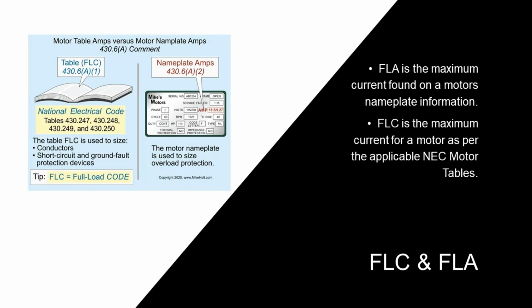All right, the only thing that we are going to size in motors with the nameplate is overloads. Conductor sizing is out of the code book. And I say overcurrent, I shouldn't have said that. I should say short circuit and ground fault protection is going to come out of the code book. Overcurrent is actually going to come out of the overloads. So I misspoke there. So read this slide here. Conductors, short circuit, and ground fault protection devices are going to come straight out of the code book.